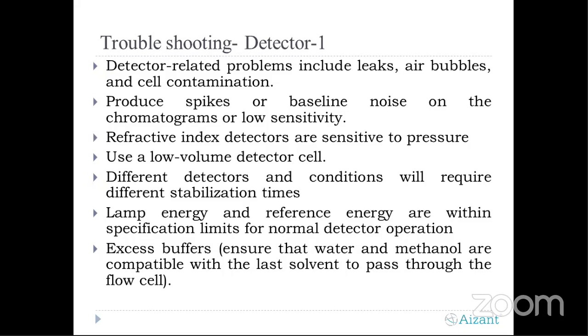The next point is that different detectors require different stabilization times. The methods which we use for an RI detector require more equilibration than UV detection. As I stated, it's a bulk property detector, so the cell or the whole system takes more time to equilibrate on RI compared to UV. If you go to ELSD, evaporative light scattering detection, it will take more time than even the RI detector. So we have to be very precise when selecting the mode of detection. We should not put a thumb rule for all detectors that 30 minutes of equilibration is enough, or half an hour, or 1 hour. Based on your methodology, you have to estimate how much equilibration time is required. That will make us comfortable with respect to different issues in HPLC.